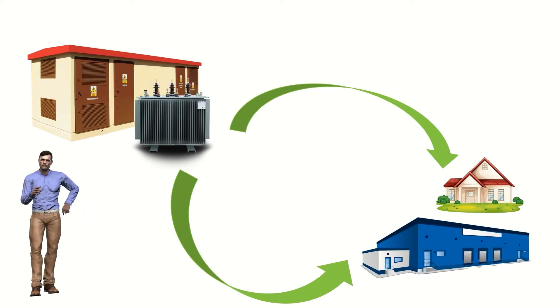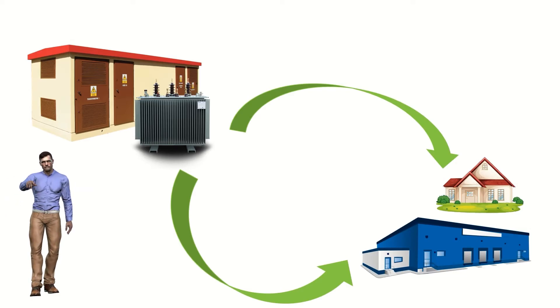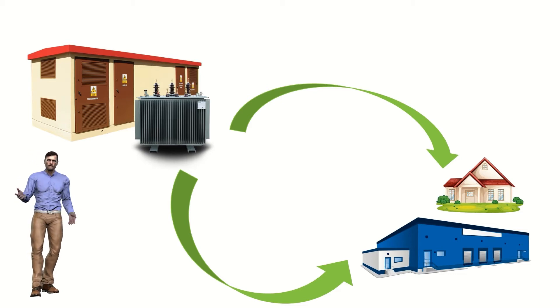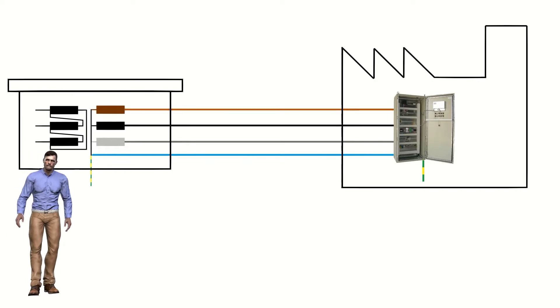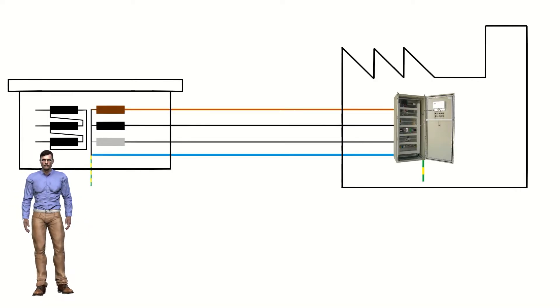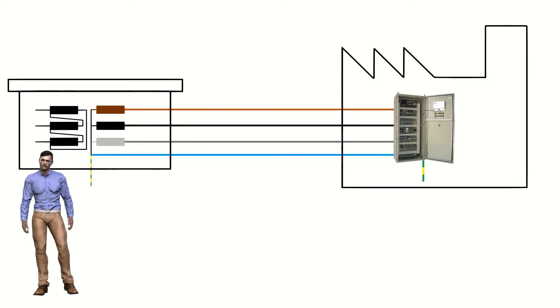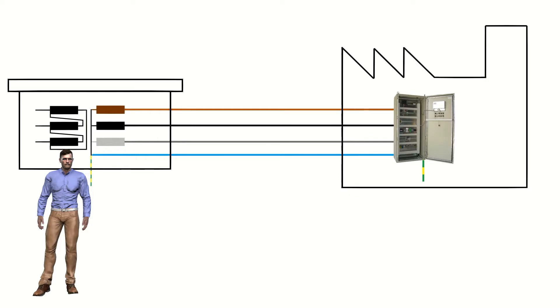In these transformation centers a transformer reduces the voltage from, for example, 30 kilovolts to the 400 volts AC that we have mentioned. From the transformation center, the electrical energy will be transported to the users through three-phase lines made up of three cables for each of the three phases, and an additional neutral cable, so that we will be able to supply three-phase loads such as motors, or single-phase such as computers.